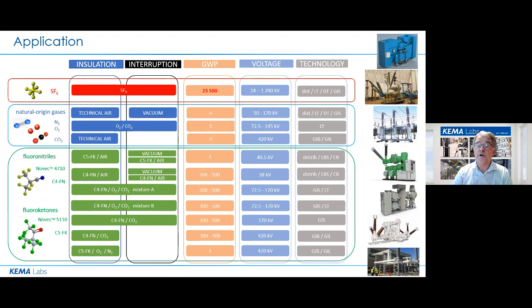As you see, insulation by SF6-free gases is far easier than interruption, since GIL projects up to 420 kV are running or are planned with all the gases. Fault current interruption is now limited to 145, 170 kV.